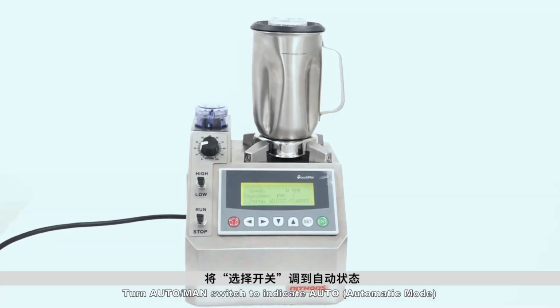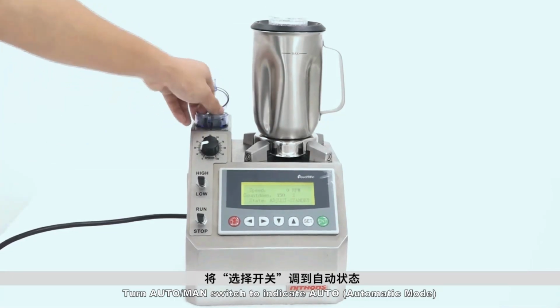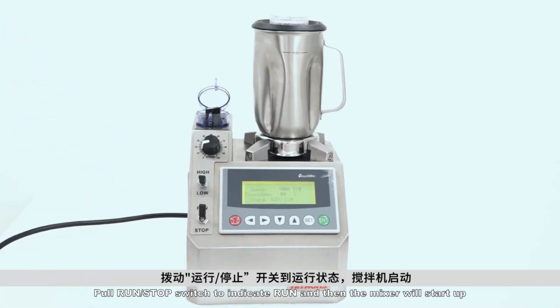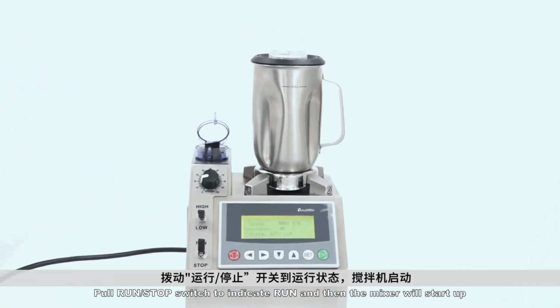Automatic mode. Turn AUTO/MAN switch to indicate AUTO (Automatic Mode). Pour the liquid required by the test into the mixing cup and weigh some cement with its mass consistent with test requirements. Pull run stop switch to indicate run, and then the mixer will start up. Start to add cement slurry evenly at once and finish it within 15 seconds.